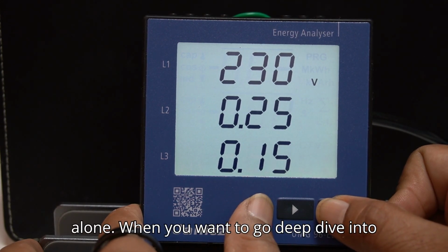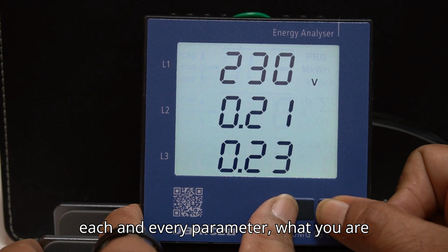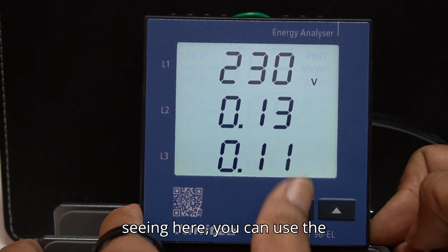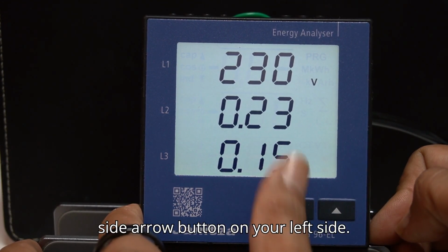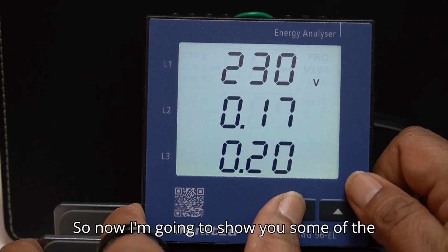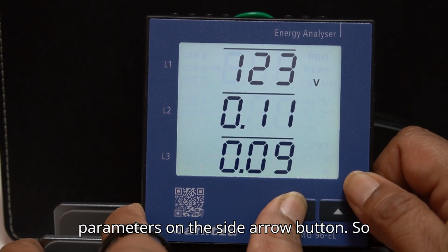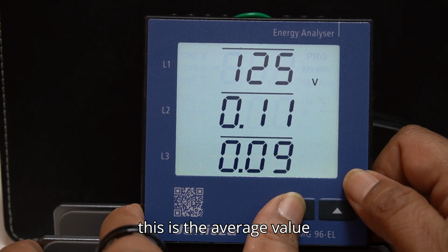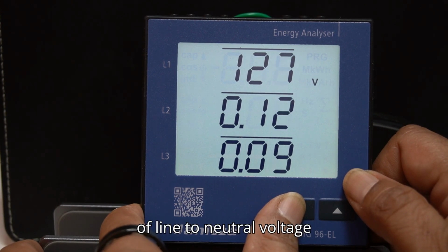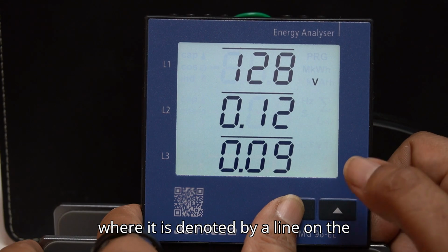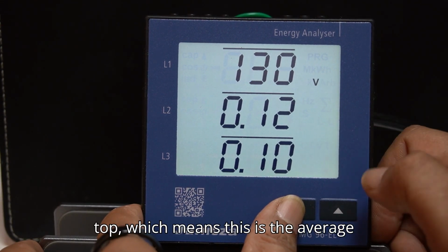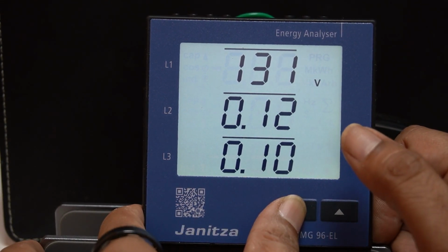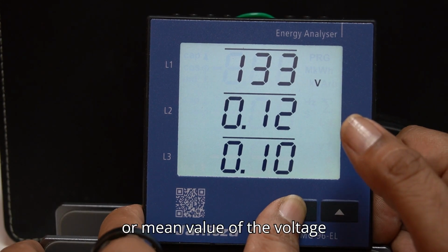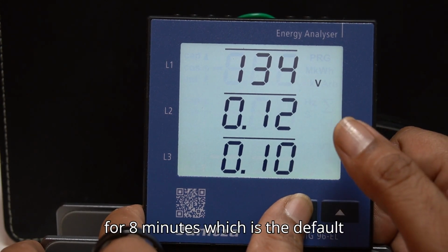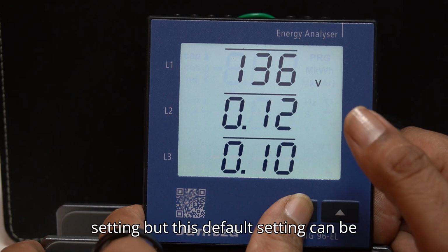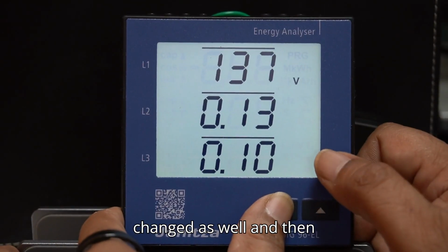When you want to go deep dive into each and every parameter that you are seeing here, you can use the side arrow button on your left side. Now I'm going to show you some of the parameters with the side arrow button. This is the average value of line to neutral voltage, denoted by a line on the top, which means this is the average or mean value of the voltage for 8 minutes, which is the default setting. But this default setting can be changed as well.